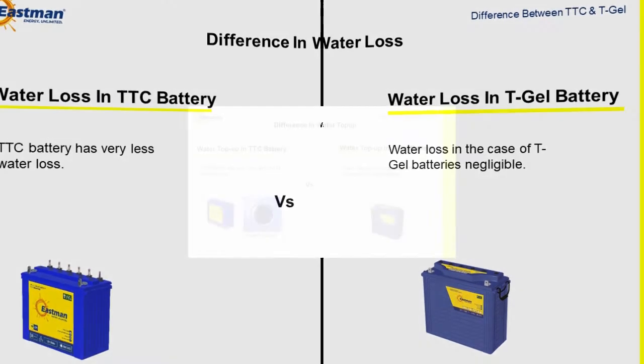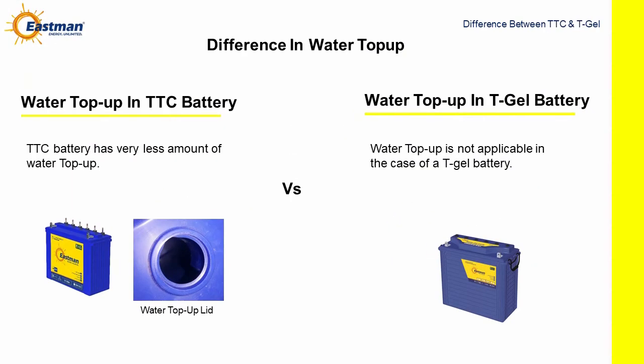Difference in water loss. TTC battery has very less water loss. Water loss in the case of T-Gel battery is negligible. Difference in water top up. TTC battery has a very small amount of water top up required. Water top up is not applicable in the case of a T-Gel battery.